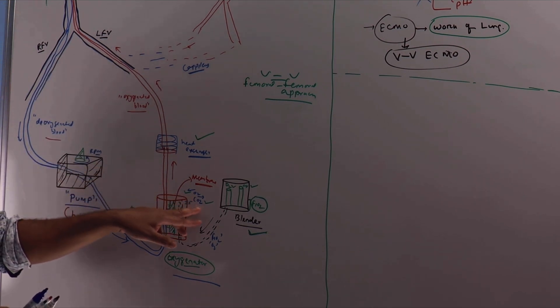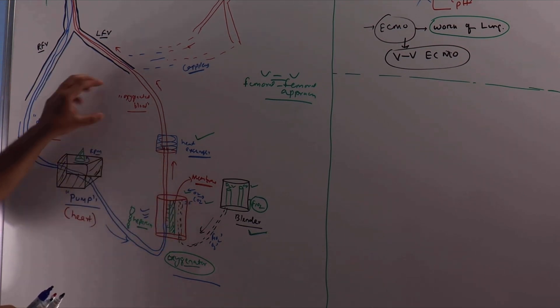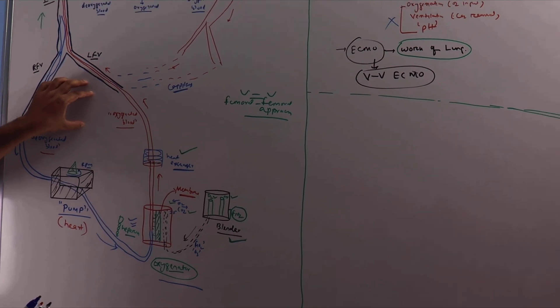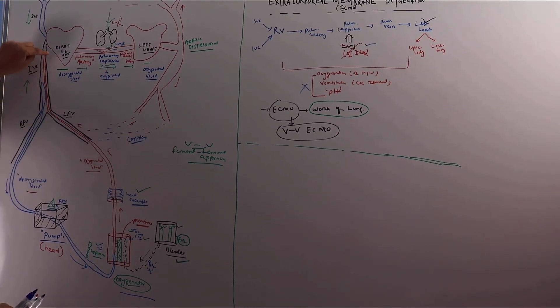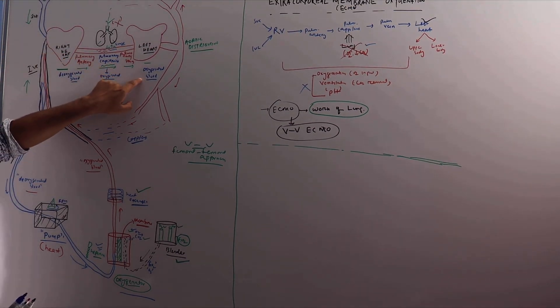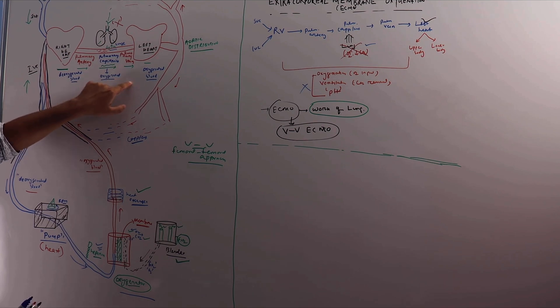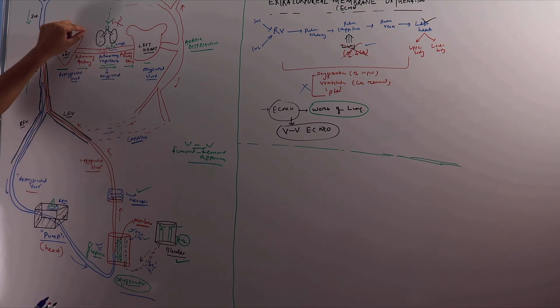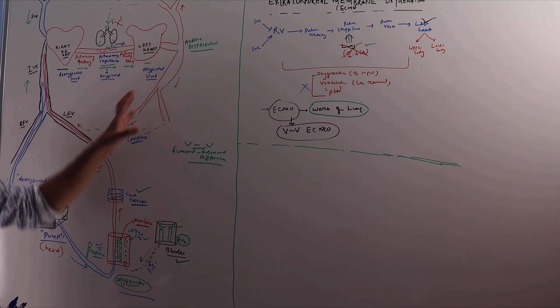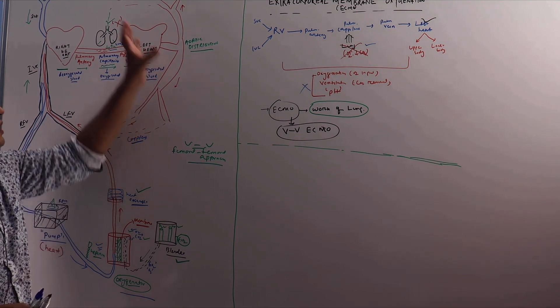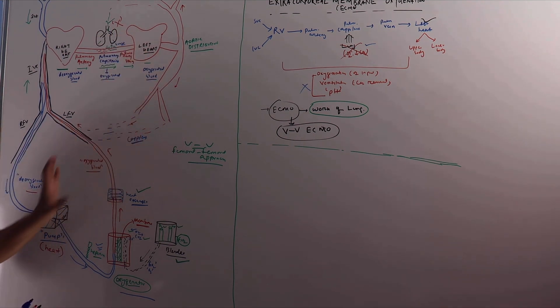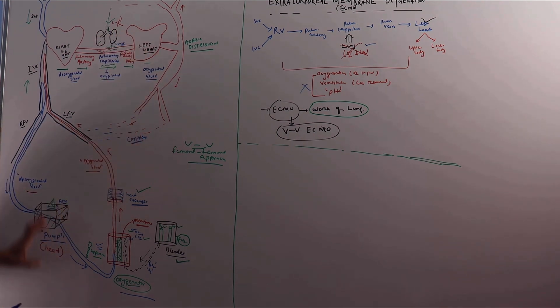Now the blood is oxygenated, it is heated, it remains clot-free because of heparin, and carbon dioxide has been washed out. We can now put this oxygenated blood into the right heart, from where it will go to the left heart via pulmonary artery, capillaries, and pulmonary vein — without needing the lung to do any work. Then the left heart can distribute the oxygenated blood to all the various organs. This is how ECMO works.